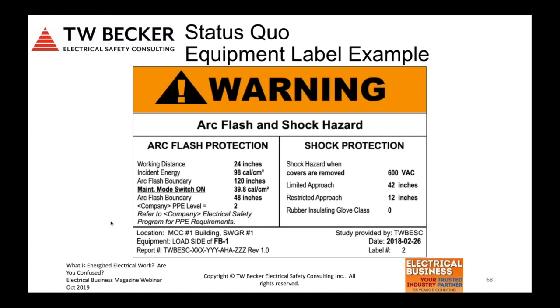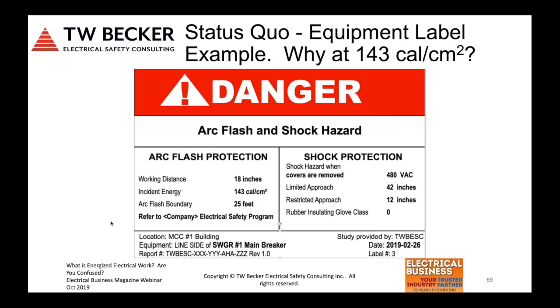So again, with these labels, you're going to see, unfortunately, hundreds of different specifications for them in industry right now. As far as moving from the warning signal word to danger, technically, when we do a risk assessment, an arc flash is available up to 140 calories, right? So that's when the label would change from warning to danger.